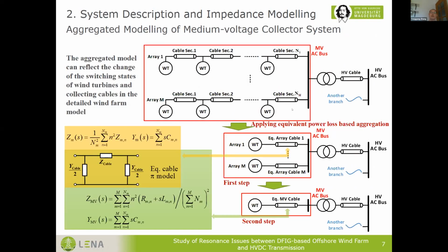As for the aggregated modeling of the medium voltage collector systems, all the wind turbines can be considered in direct parallel connection due to the negligible series impedances of the collecting cables. Then they can be aggregated to a single wind turbine by scaling their parameters. And applying the equivalent power loss-based aggregation, as well as the accumulated capacitive effect of the cables, the whole MV collector system can be reduced to a single machine system. In the end, the aggregated model can reflect the change of the switching states of wind turbines and the cables in the detailed wind farm model.